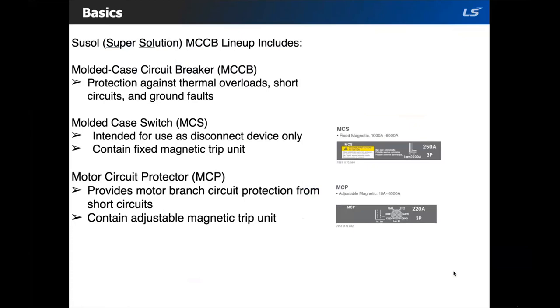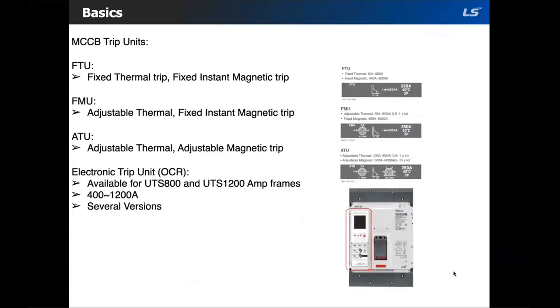Then there is the motor circuit protector, or MCP. As the name implies, they are intended to protect motors. MCPs are an instantaneous circuit breaker that contain only an adjustable magnetic trip unit. Now that we understand the different offerings within the MCCB family, let's cover the various trip unit options. For the UTS100, UTS150, 250, 400, and 600 amp frame sizes, there are three types of trip units.